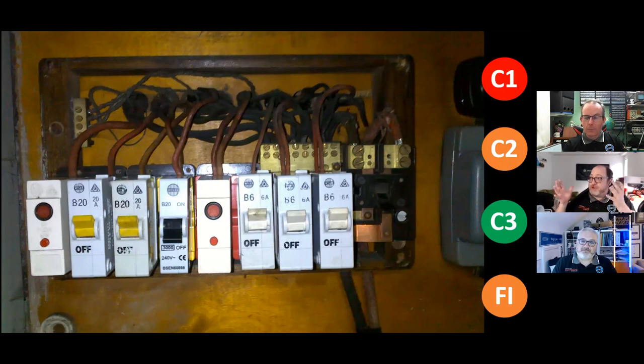So this is a classic. All right, the cover is off on this one, yeah? The cover is off, by the way. It wasn't found like that. So this is one of the classic Wylex boards that John Ward owns. It's a vulcanized Indian rubber supply. Wooden frame. Those who may not have seen that, which is just the tails here on the main switch. It's a double pole isolator. And this used to be full of rewirable 3036s. And then Wylex, in their wisdom, came up with the 3871 push fit, and it's been upgraded with the 60898 trip switch equivalents with the 3kA rating.